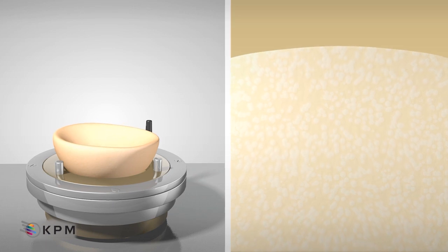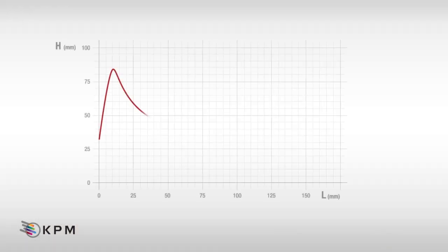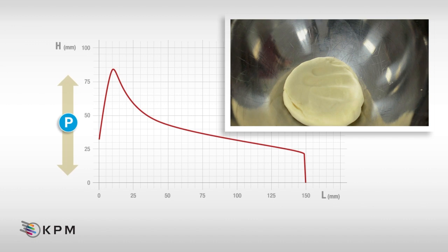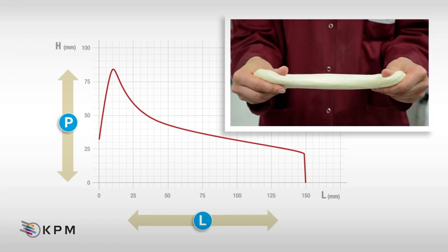The Alveograph can be used to analyze all types of wheat – soft, hard, and durum. It provides four key measurements. P value represents dough tenacity – in other words, its capacity to resist deformation. L value corresponds to the maximum amount of air the bubble is able to contain and represents dough extensibility.